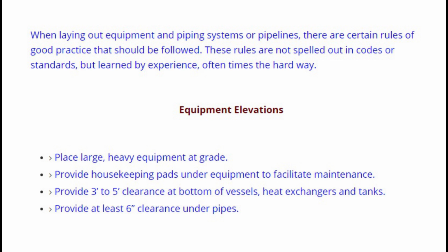Good practice for equipment elevations. Number 1. Place large, heavy equipment at grade. Number 2. Provide housekeeping pads under equipment to facilitate maintenance. Number 3. Provide 3 feet to 5 feet clearance at bottom of vessels, heat exchangers and tanks. Number 4. Provide at least 6-inch clearance under pipes.